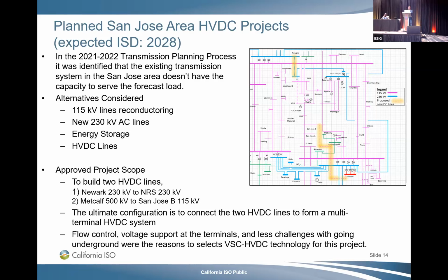These aren't interregional lines. The main driver for DC was the need for flow control, to control the flow under contingency. With an AC line, if you lose it, the remaining line gets overloaded. With DC, you can control the flow under contingency conditions. There's also potential for undergrounding, which is easier with HVDC, and with VSC HVDC you get voltage support at both terminals, essentially a STATCOM at each connection point.